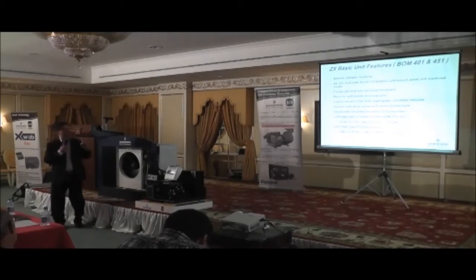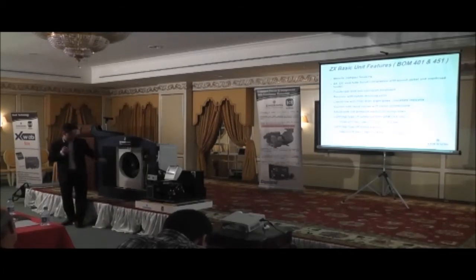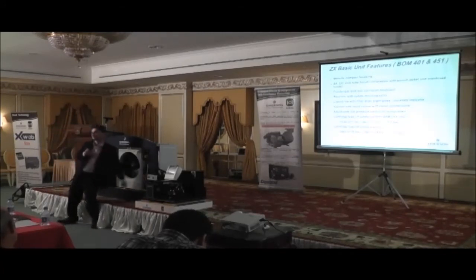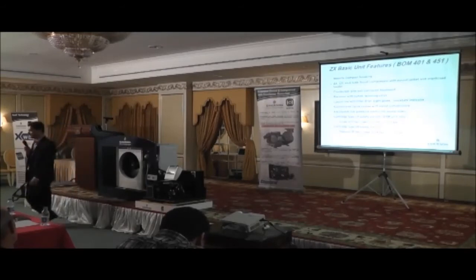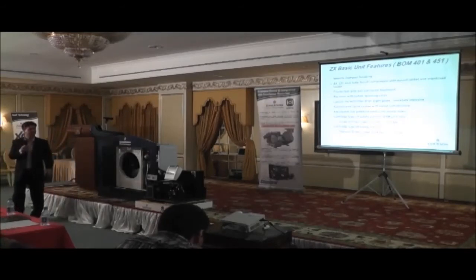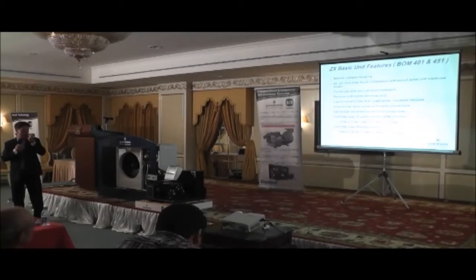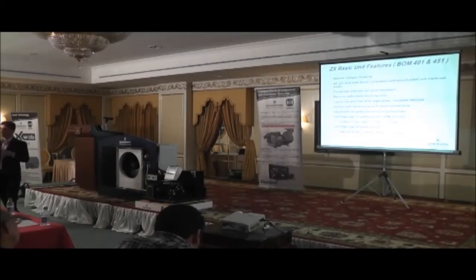There is one adjustable low pressure switch for pump down. This is it here, low pressure switch. In terms of the safety, on the ZX unit we've got an LP safety switch. It's an encapsulated switch, which means you cannot adjust it. The settings are preset. So we've got an LP for the medium temp, and for the low temp, it's not fitted in there. And then we've got an HP switch for both the medium and the low temp.